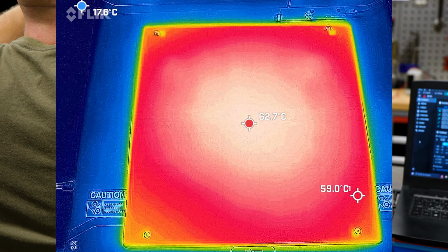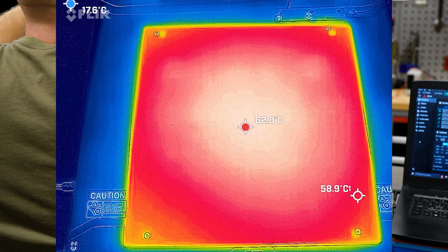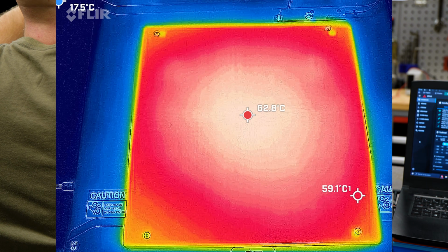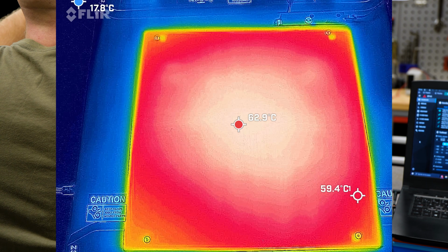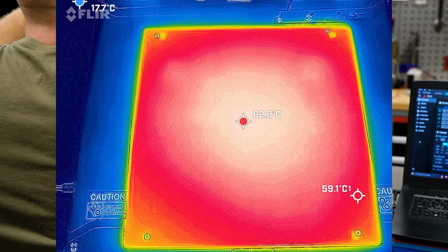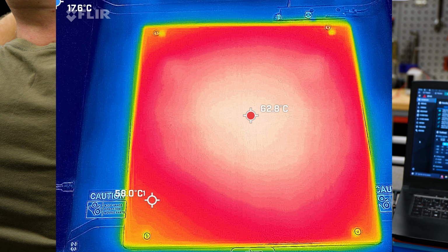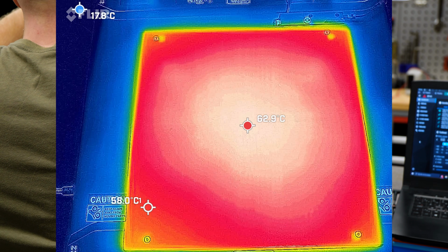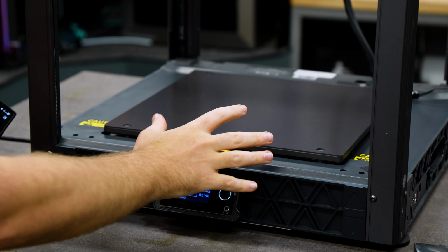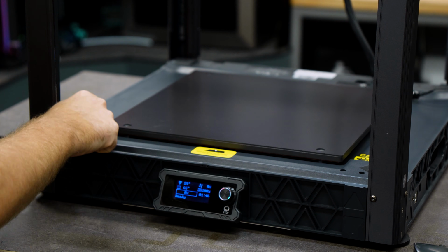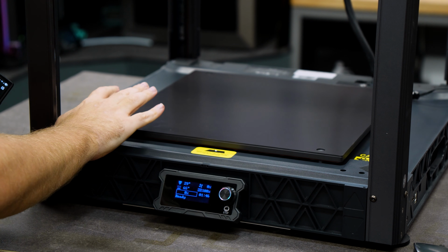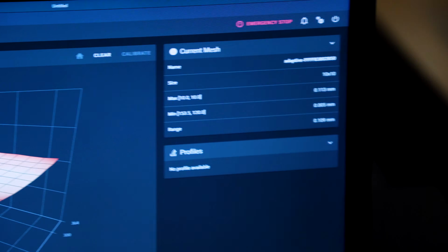This is going to be the bed heating of the graphite bed. We can see a maximum temperature of 62 degrees in the middle with 59 degrees on the side. But we can also see right here on the left, we do have a little bit more of a cold spot. So judging from the thermal camera, we can see that this corner right over here is a little bit colder than all the rest.